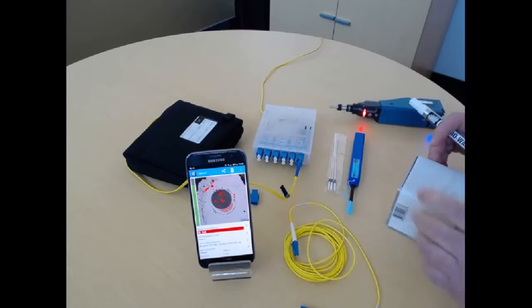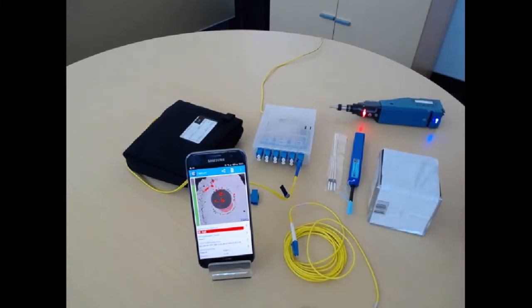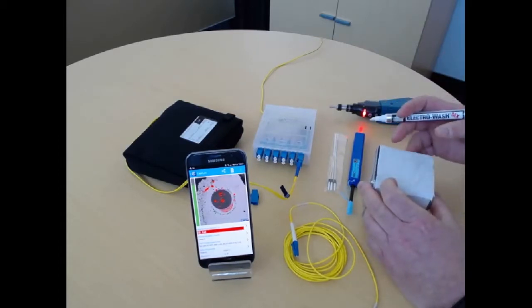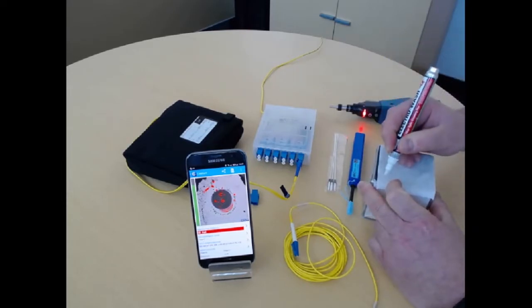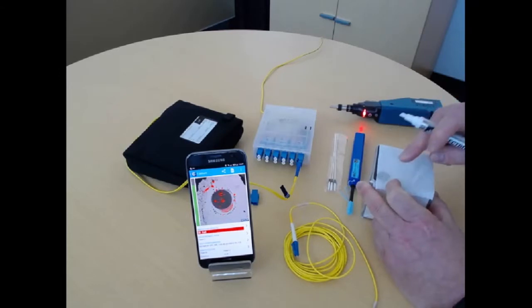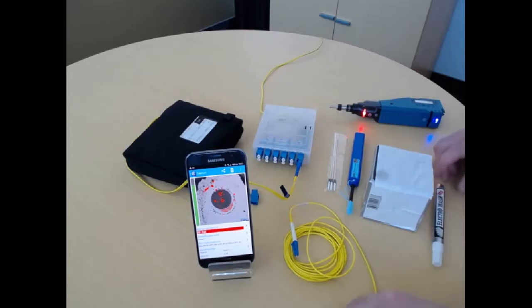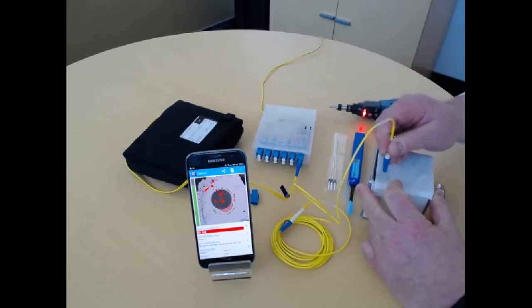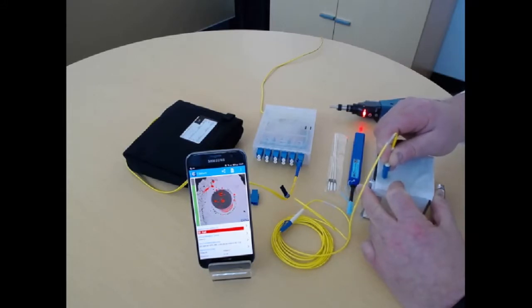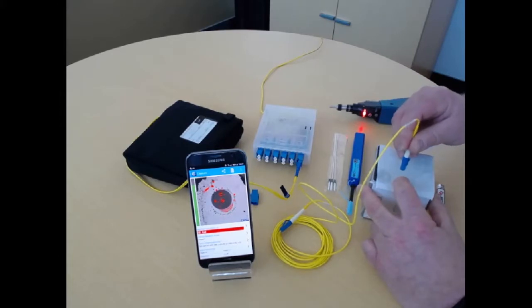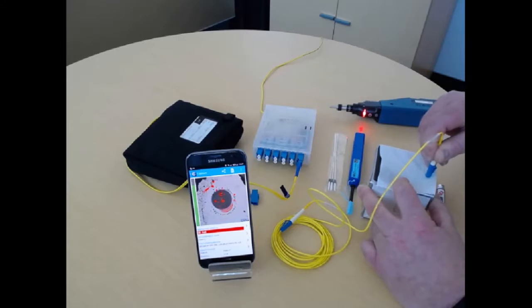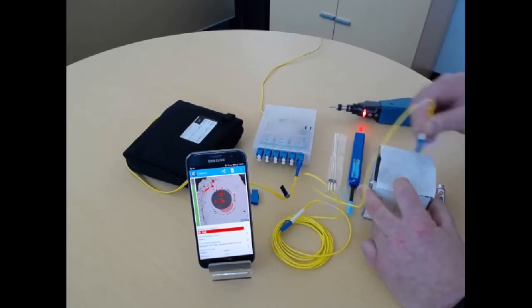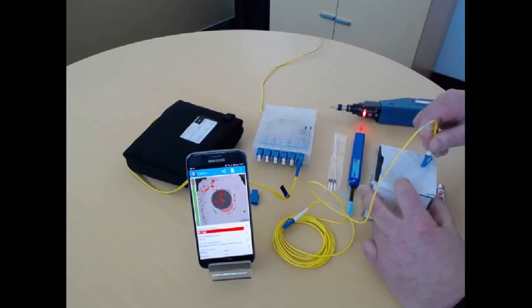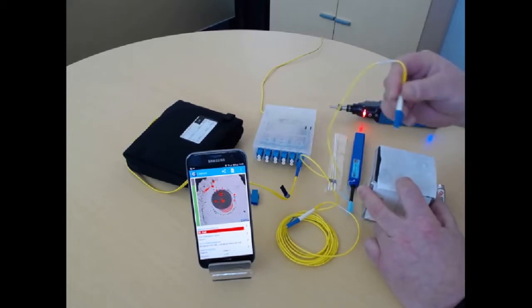So what we do is use the wet dry cleaning solution. I use my swipe cube. I use my electrowash pen and I put a solution, as you see, that's the wet solution, in the corner of my wipes. So I'm going to use my single connector to apply the wet solution, doing little circles with the connector, wiping on the wipes and touching the solution. And I take the dry surface of my cloth or wipe, and I draw vertical lines, four lines, to dry or polish, let's say, the interface of my connector.